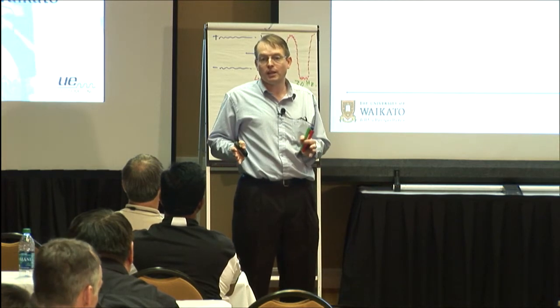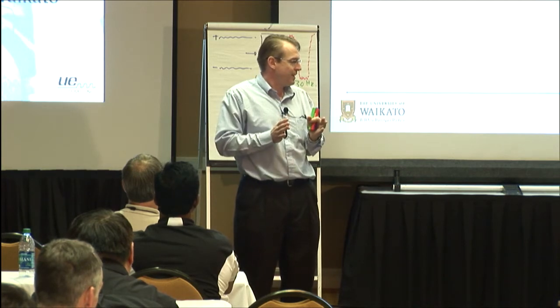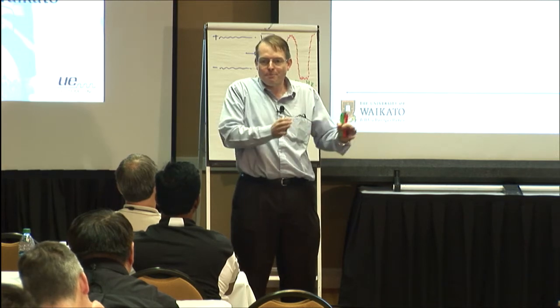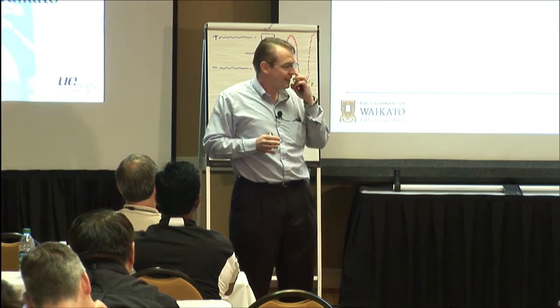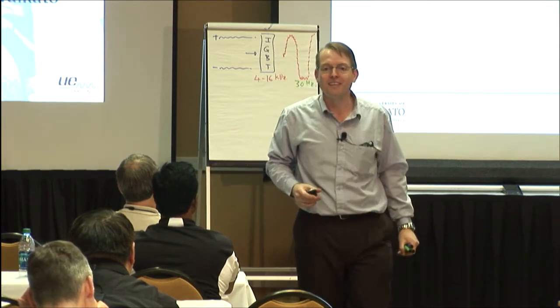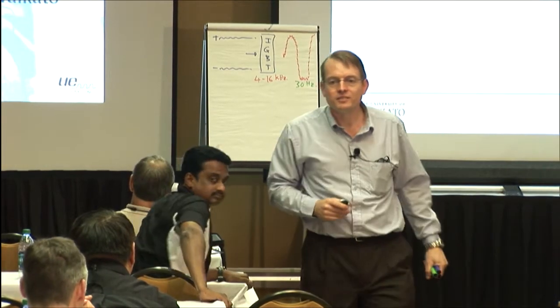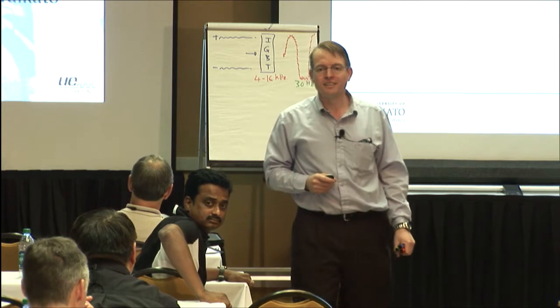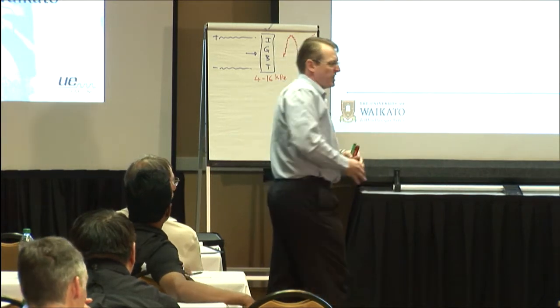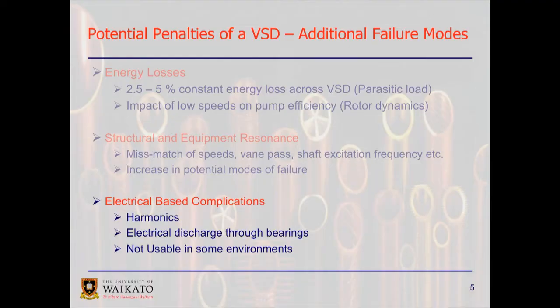The early VSD air compressors were speed windowed. The first thing they did is they just blacked out those speed bands. So the first VSD air compressors used to jump, you know, from one band to the next to avoid those points. Not the smartest and smoothest way, but that was how they overcame it. Yes? I was just going to say that's what we've done. Yes. At a certain speed that motor will start to shake, and they just block that out. Yeah, okay. Not the most elegant solution, but hey, if that's what you got to do, you kind of just lump it, right? Okay.